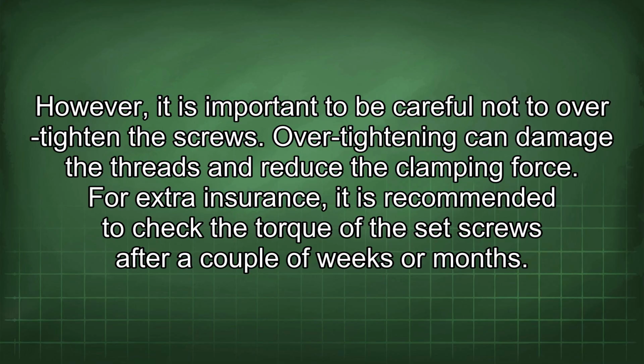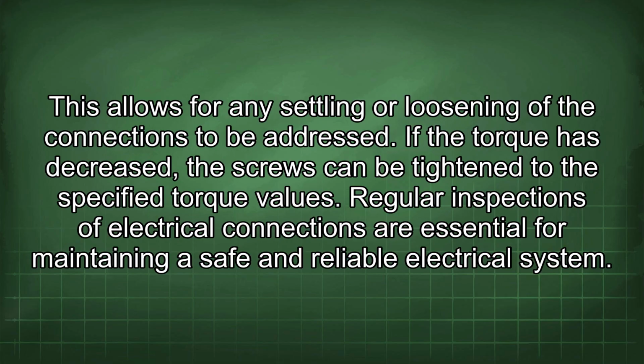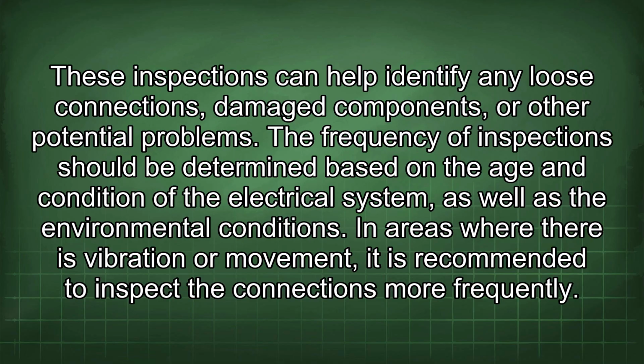For extra insurance, it is recommended to check the torque of the set screws after a couple of weeks or months. This allows for any settling or loosening of the connections to be addressed. If the torque has decreased, the screws can be tightened to the specified torque values. Regular inspections of electrical connections are essential for maintaining a safe and reliable electrical system. These inspections can help identify any loose connections, damaged components, or other potential problems. The frequency of inspections should be determined based on the age and condition of the electrical system, as well as the environmental conditions. In areas where there is vibration or movement, it is recommended to inspect the connections more frequently.